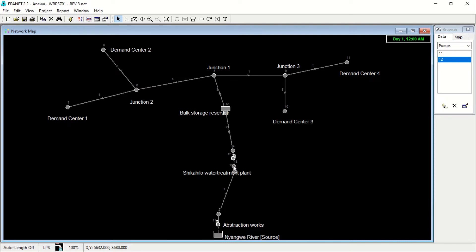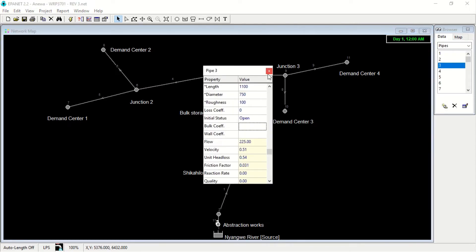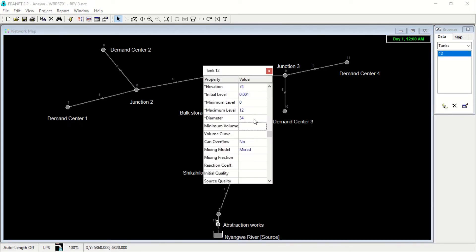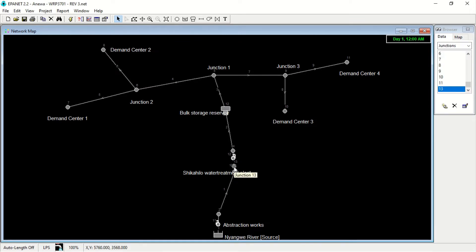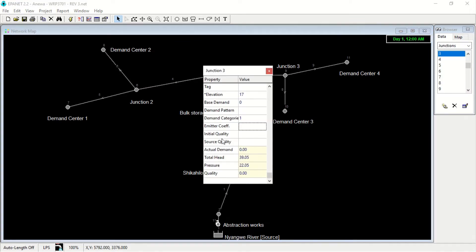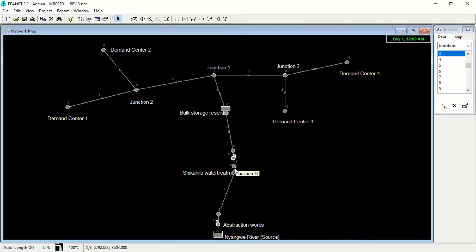Then we have another pump here. The reason for this pump is because this elevation is lower than this elevation here. When you double click, you can see that the tank has an elevation of 74 here, and then here at the Shikahilo, we can see an elevation of 17. So the water needs to flow from here to the bulk storage — that's why we need a pump here to help the water to flow.